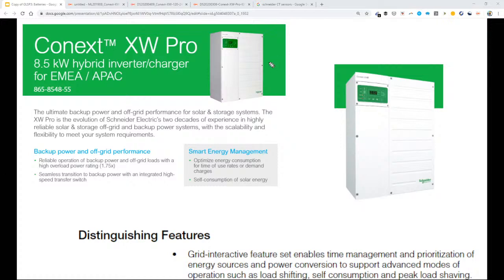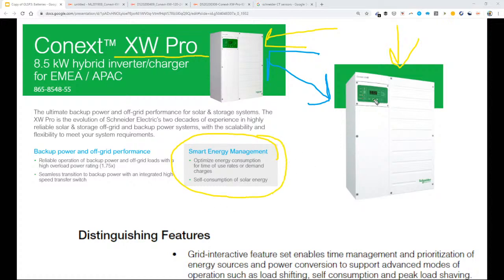These two inverters are not the same inverter. This is their old battery inverter, and this is their new battery inverter — as you can tell, they're much different from each other. If you open up the XW Pro spec sheet, it advertises smart energy management. But if you open the old XW Plus spec sheet, its features have been scrubbed away, and it no longer advertises what's directly mentioned in its manual, like load shifting, peak load shaving, self-consumption, and time of use grid sellback.